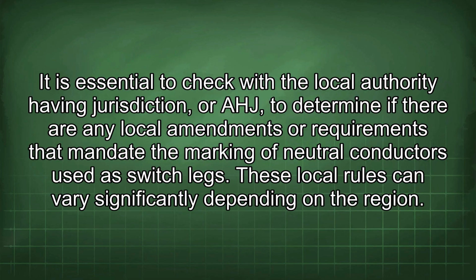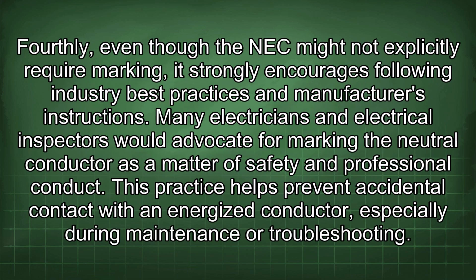It is essential to check with the local authority having jurisdiction, or AHJ, to determine if there are any local amendments or requirements that mandate the marking of neutral conductors used as switch legs. These local rules can vary significantly depending on the region. Fourthly, even though the NEC might not explicitly require marking, it strongly encourages following industry best practices and manufacturers' instructions. Many electricians and electrical inspectors would advocate for marking the neutral conductor as a matter of safety and professional conduct.